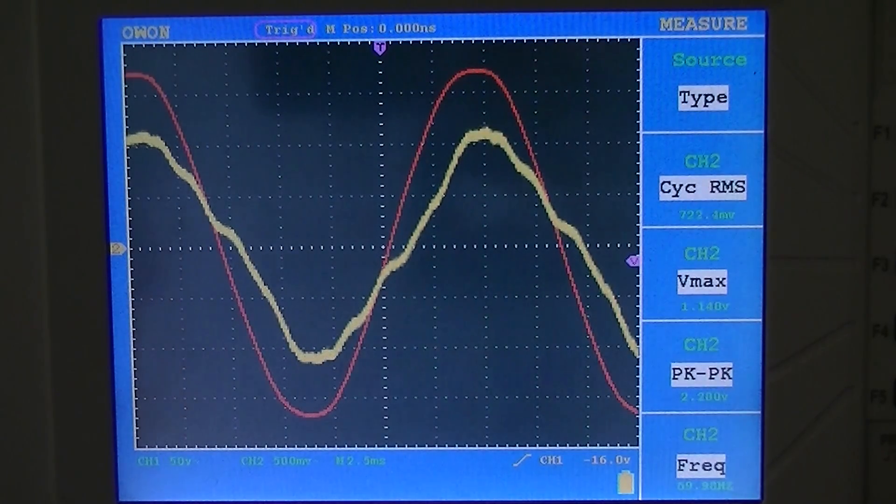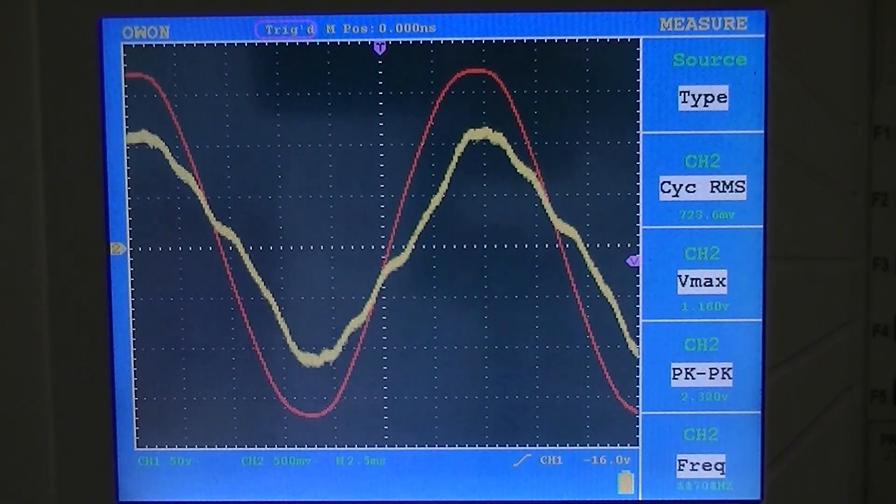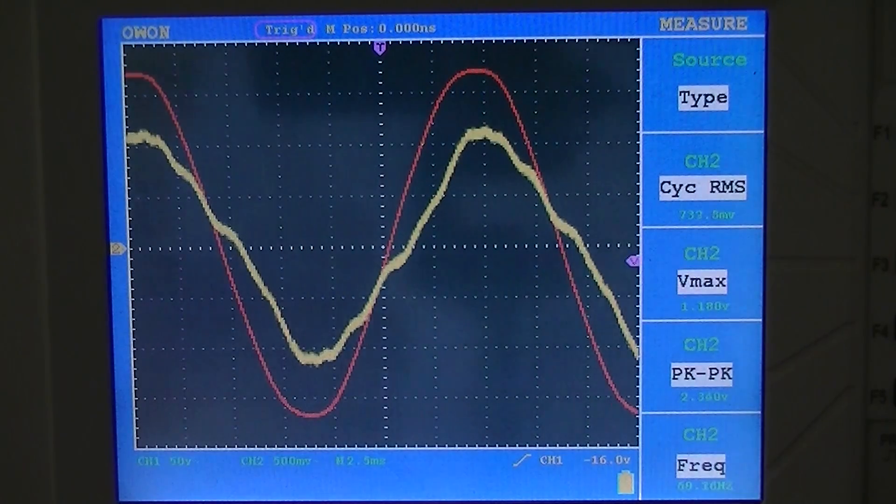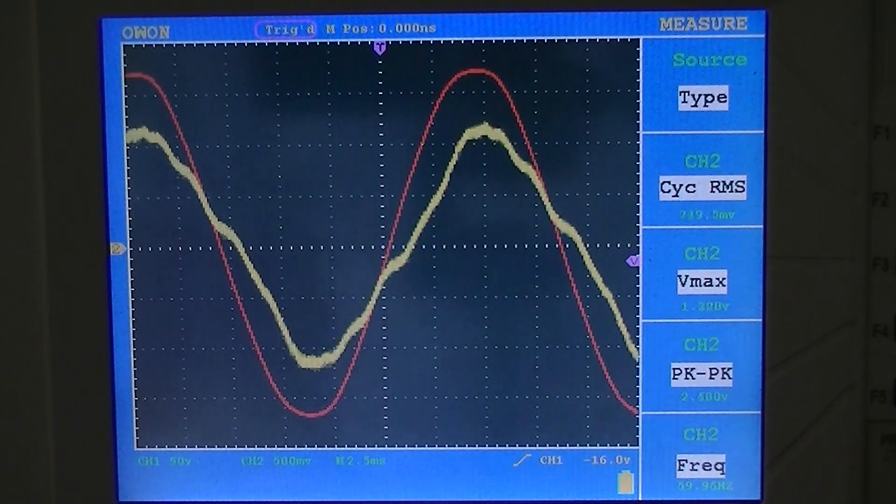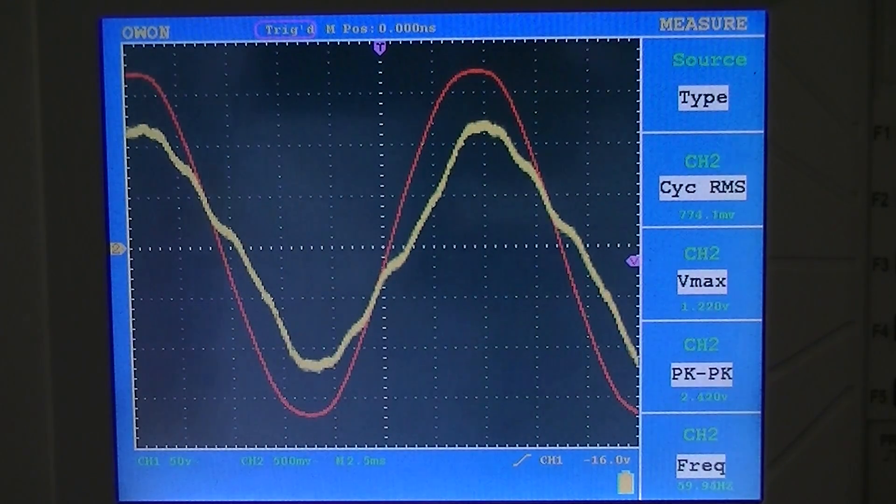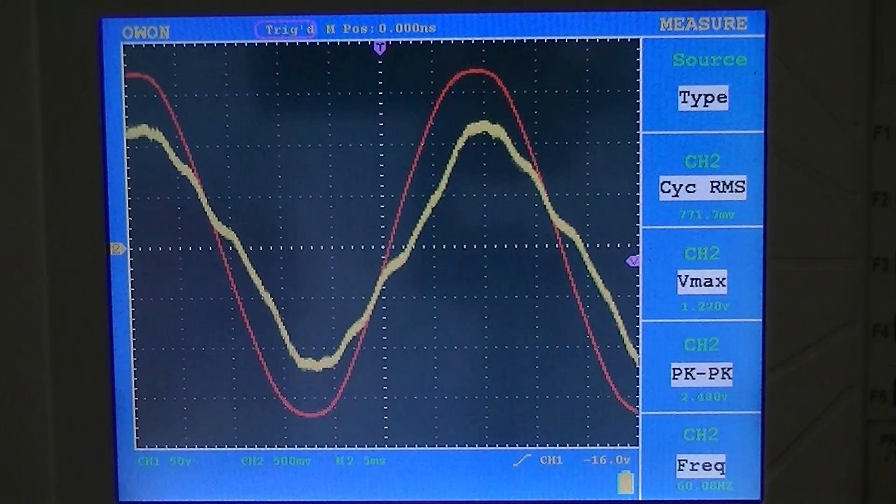And I've been wondering for a while how to establish where this voltage is coming from. And this is the test I devised to figure out the resistance and impedance of the neutral connection. So, off-screen, I have a 1500 watt load. It's an electric kettle. You can also use an electric heater. Just as long as it's 1500 watts and it's plugged into one phase, I'm going to switch it on.